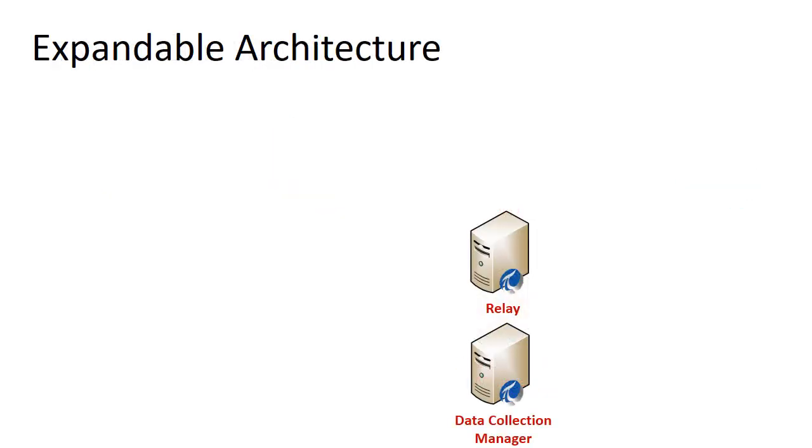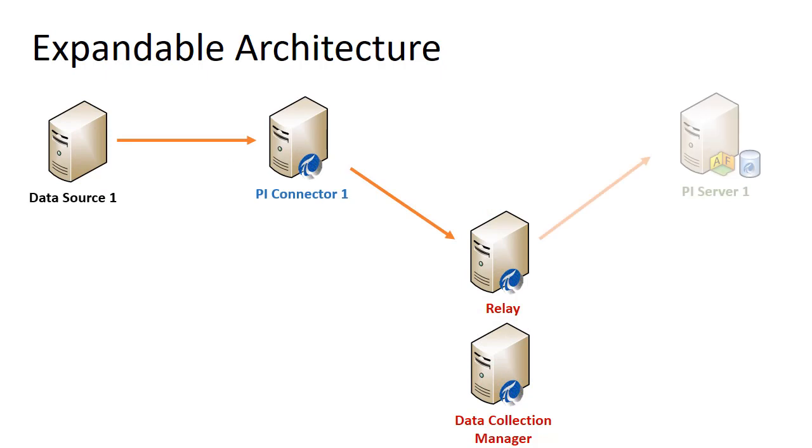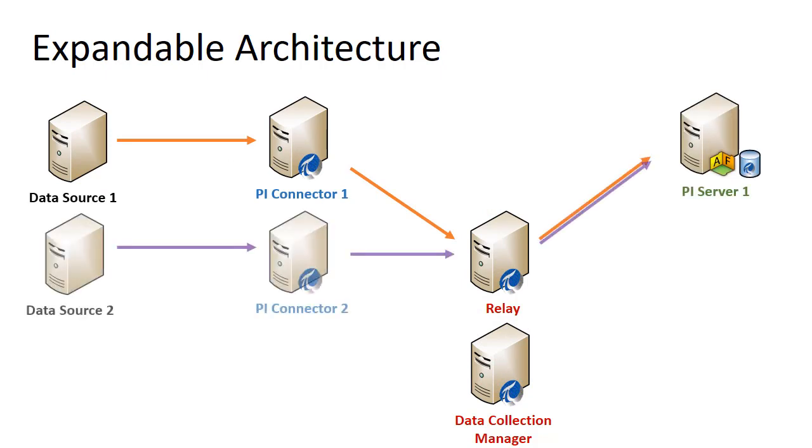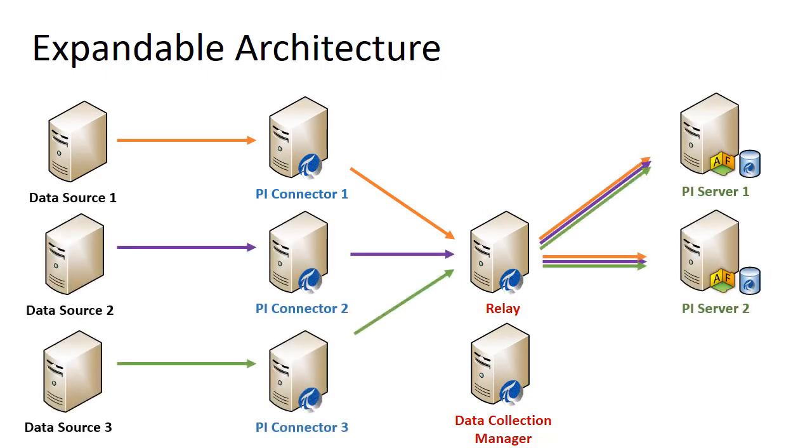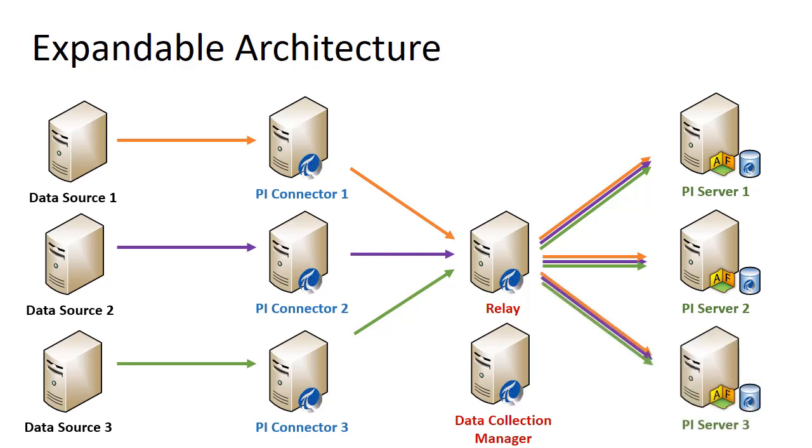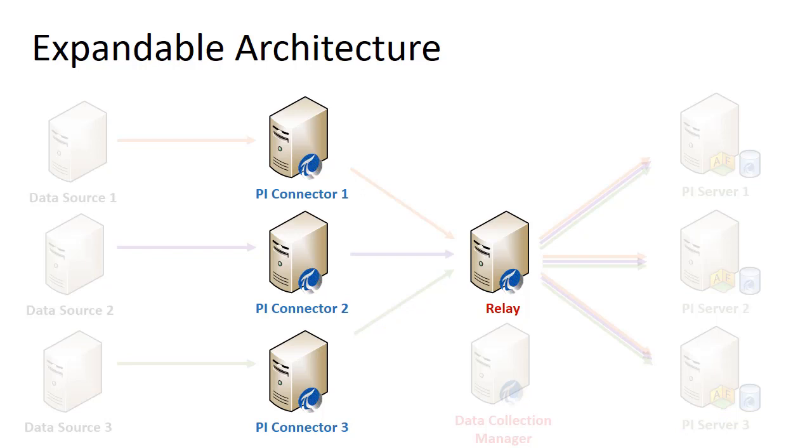Data collection manager can be used to register multiple PI connectors to a single relay. All of your connectors can then be forwarded to multiple PI servers with full awareness of PI server collectives. Each connector and the relay also have built-in buffering to protect from data loss across multiple network connections.